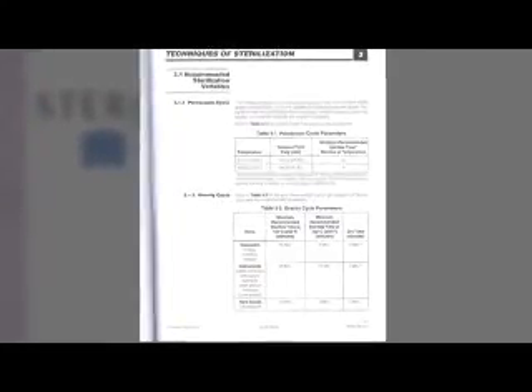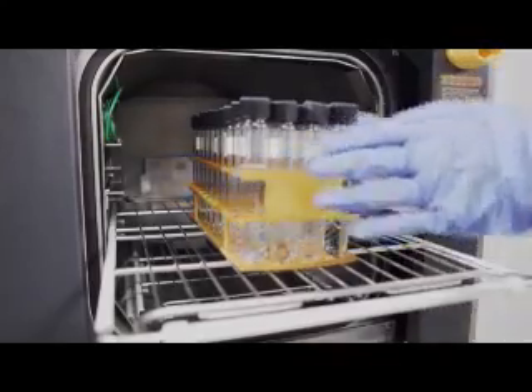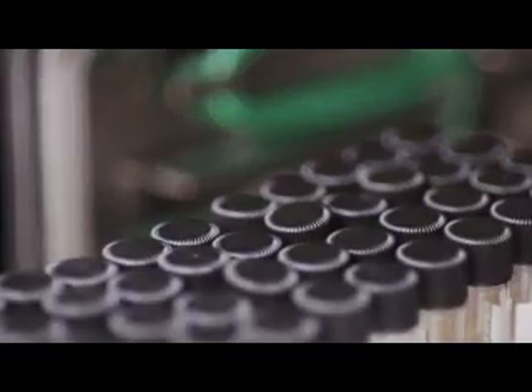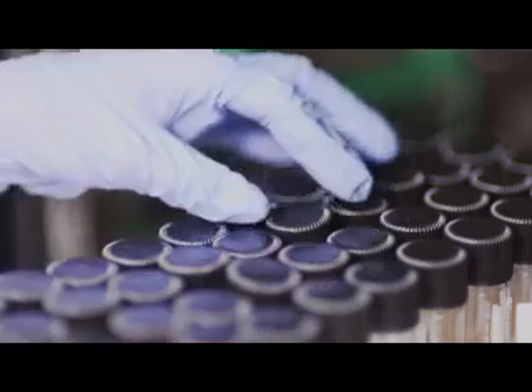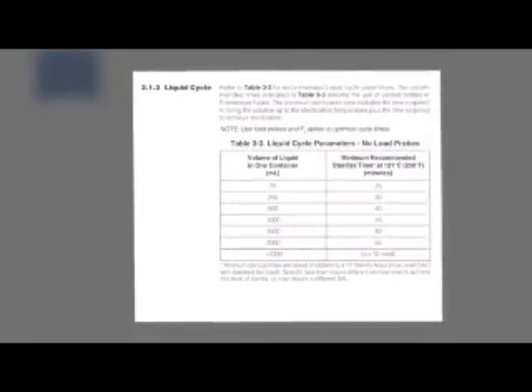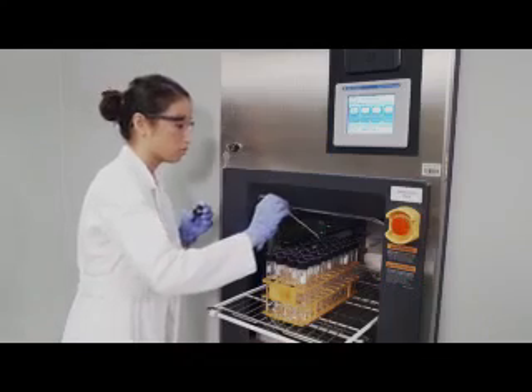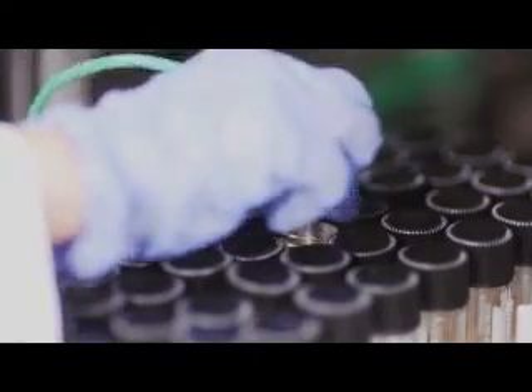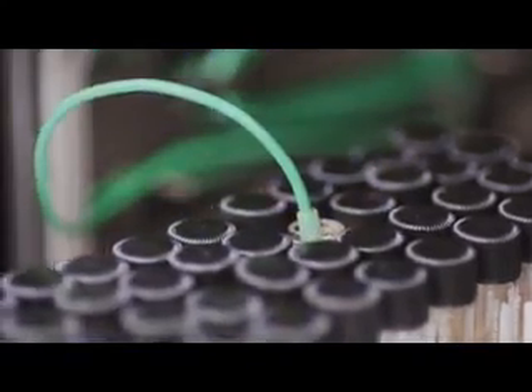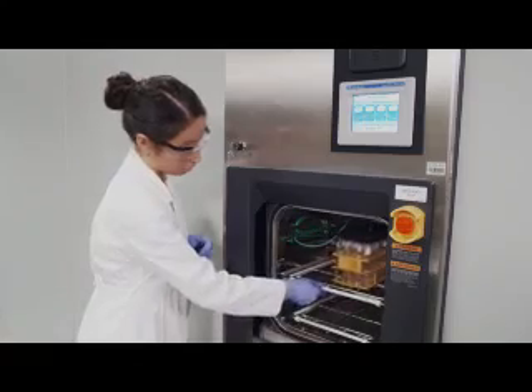Please consult your operator manual for appropriate sterilization times for various volumes of liquid and for a full list of safety warnings. Pay particular attention to how liquids are loaded. If liquids are loaded with no space between containers, set the sterilization time for the total combined liquid volume. If space can be left between the containers, then the time can be set for the volume of one container. If you are using an optional load probe, then this is not applicable, as the control regulates the time based on the temperature reading of the probe.